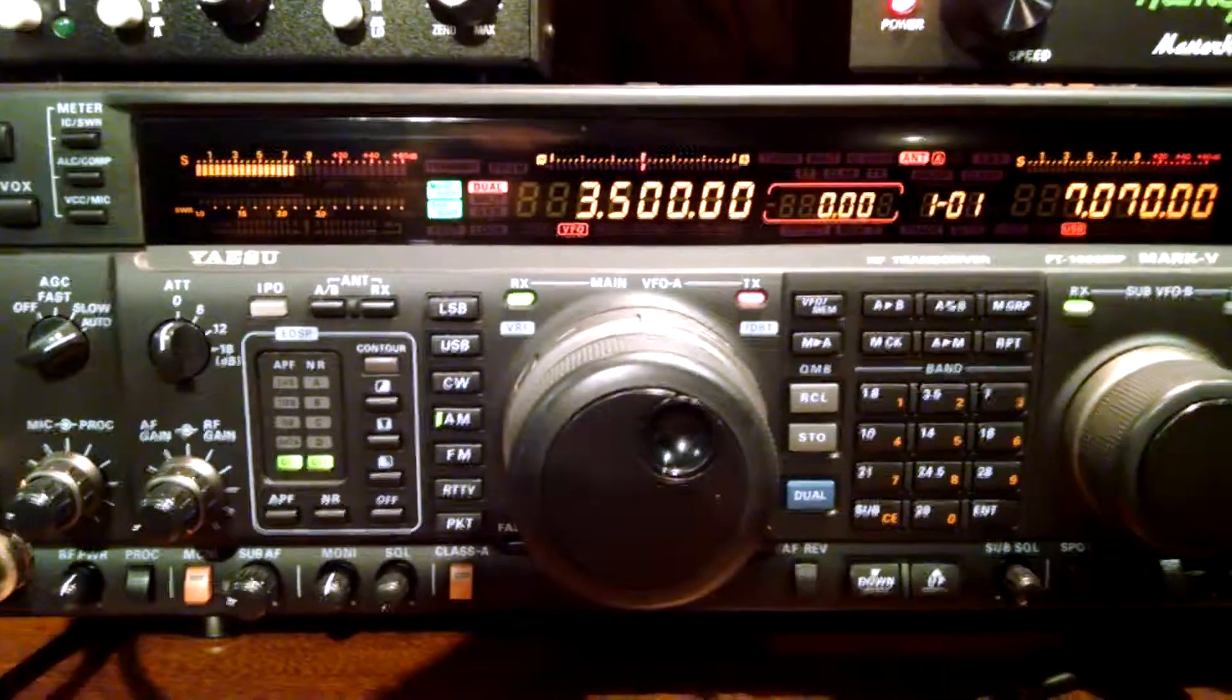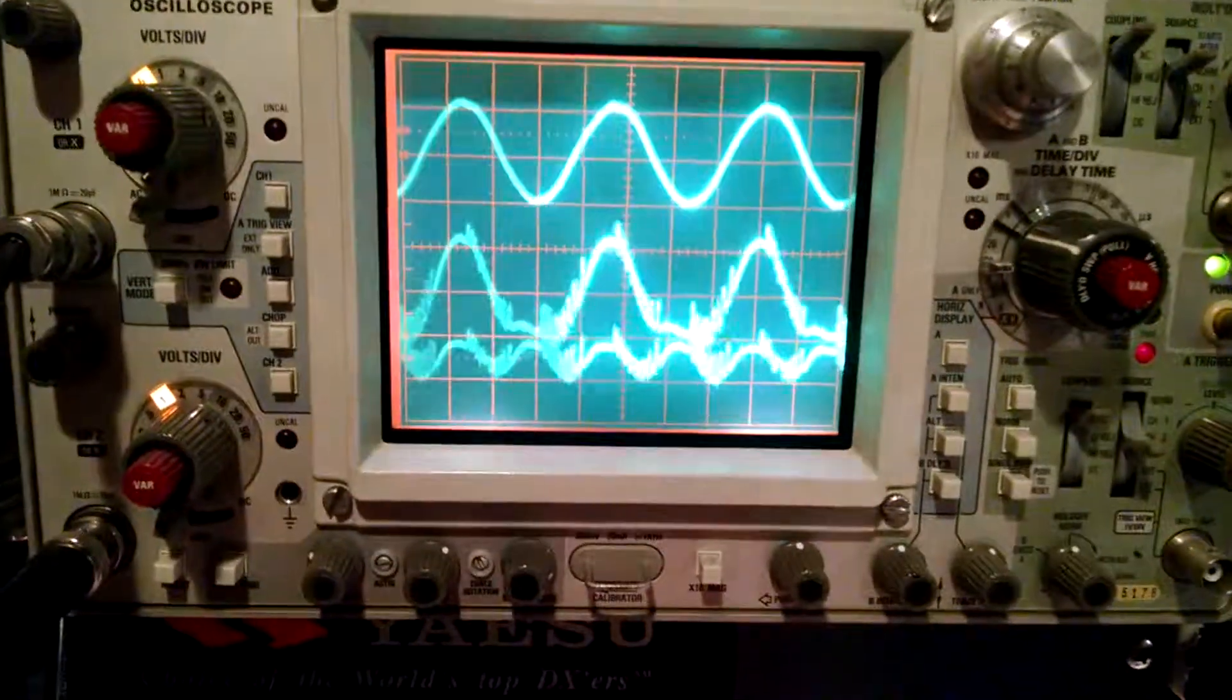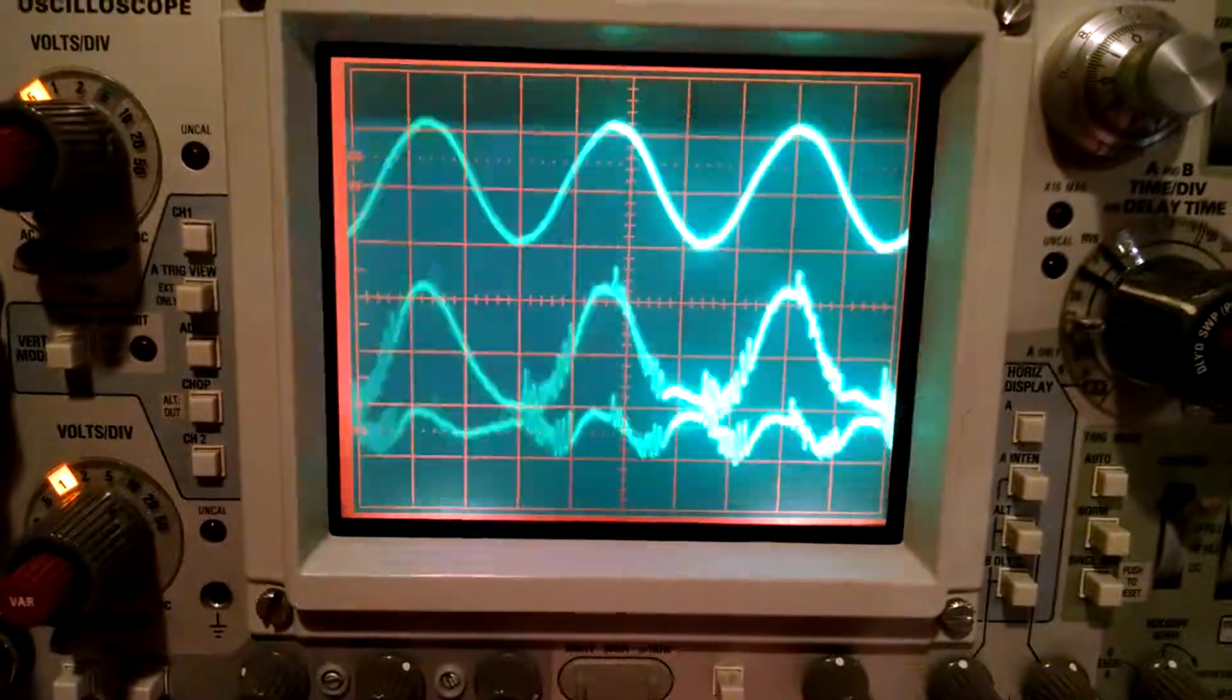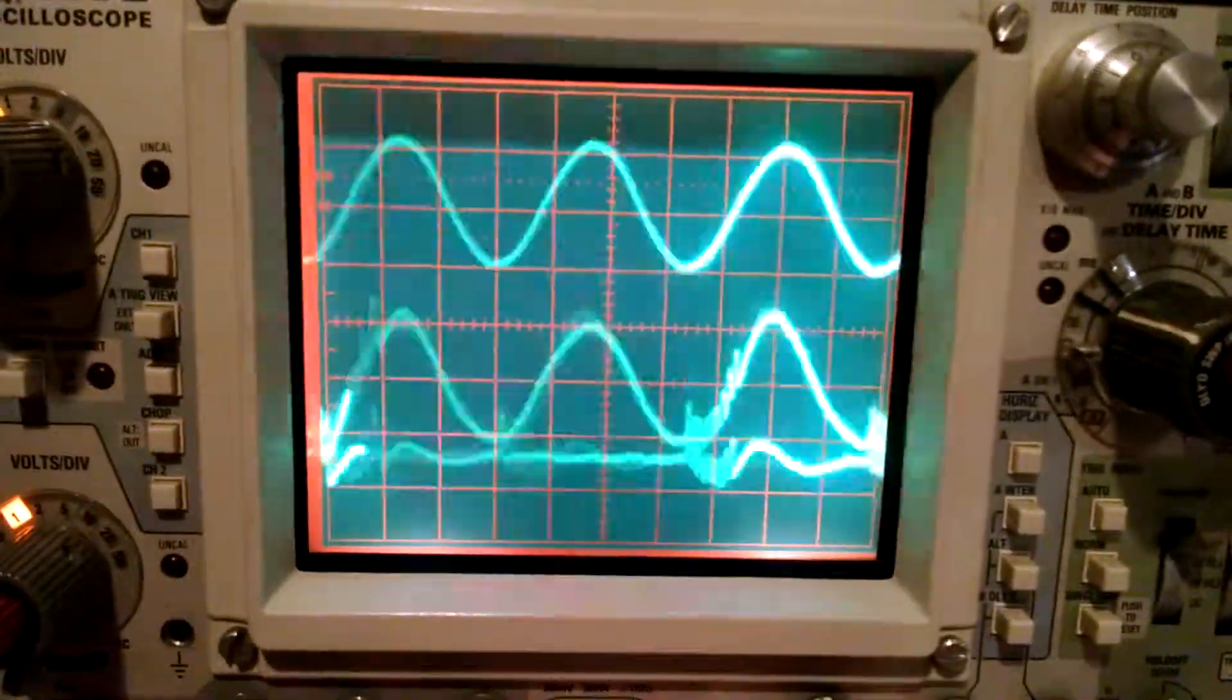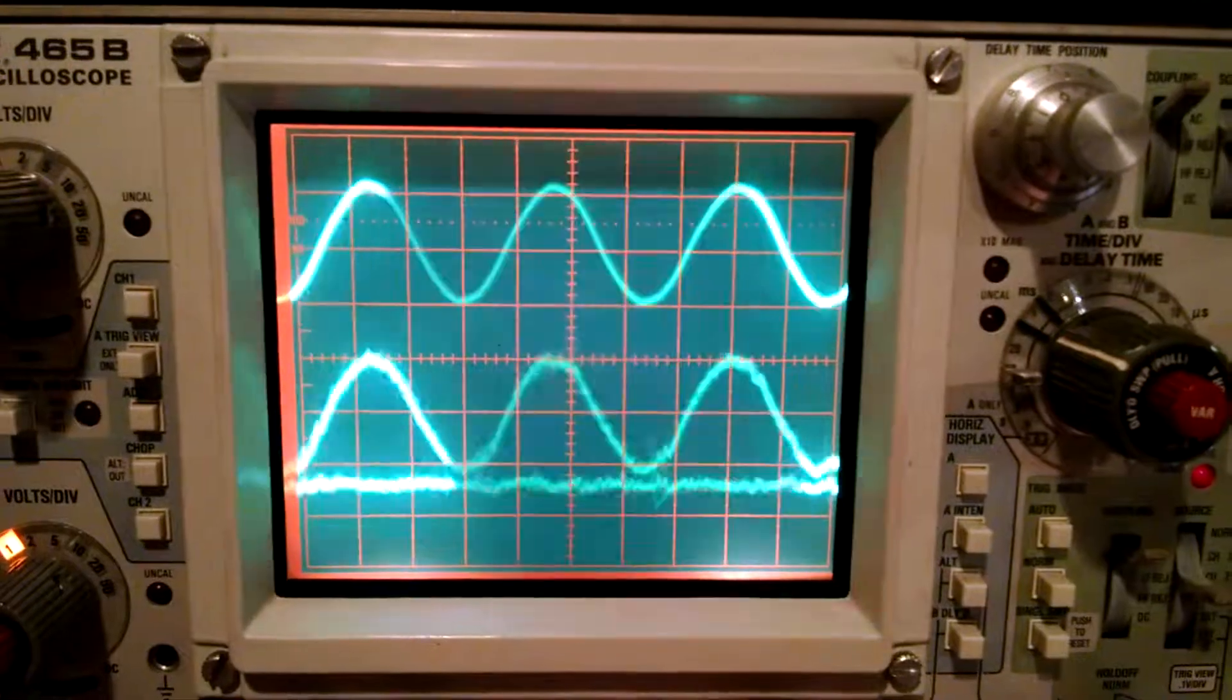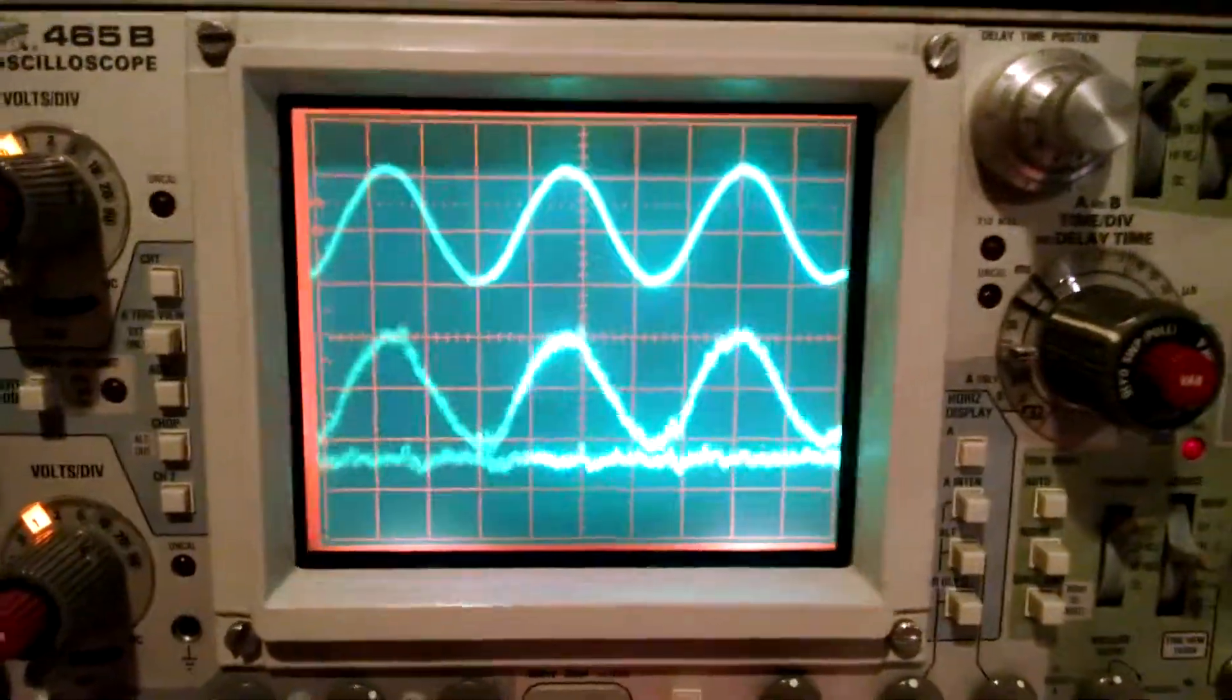Here's the trace with the noise really predominant. At every zero crossing, you have arcing that's going on. At the top of my street are 115-kilovolt lines and normal distribution lines, so I suspect it's a bad insulator or loose connector.